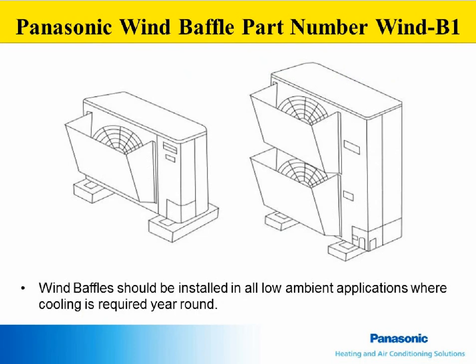In some instances, a wind baffle is needed, and one is available from Panasonic, or it can be field supplied. Controlling wind through the coil and heating or low ambient cooling is very important in some installations. If multiple outdoor units are installed, the wind baffle can also be used to divert discharge air upward and keep it from blowing into another unit's intake.